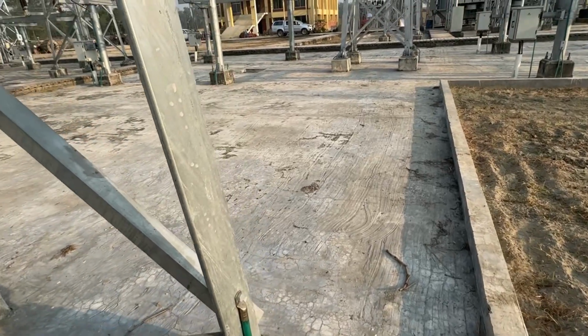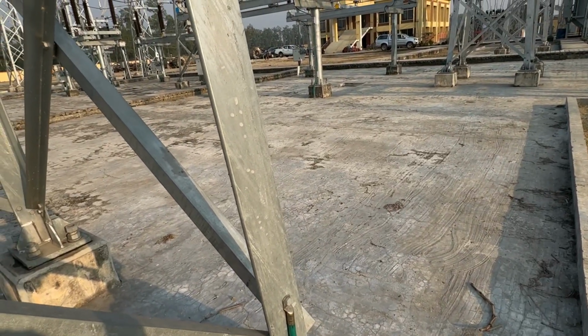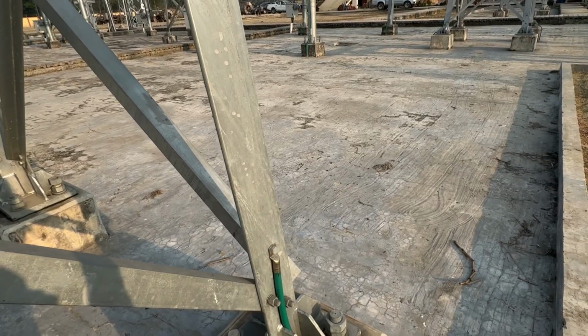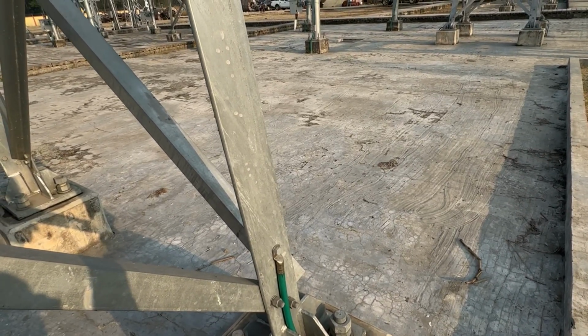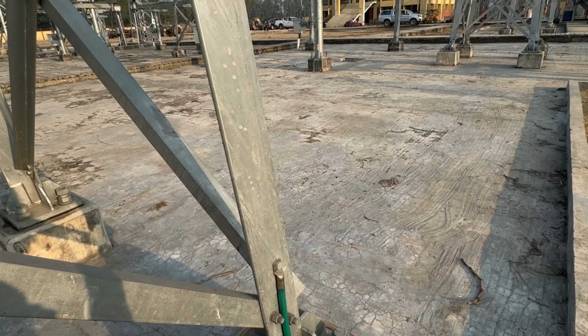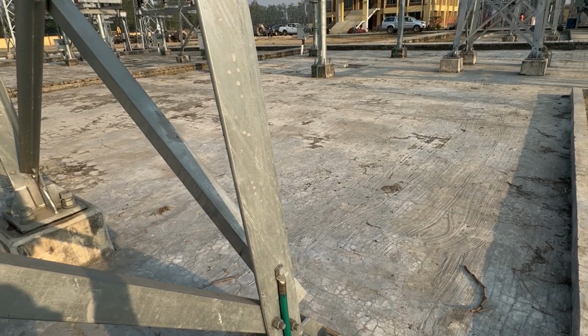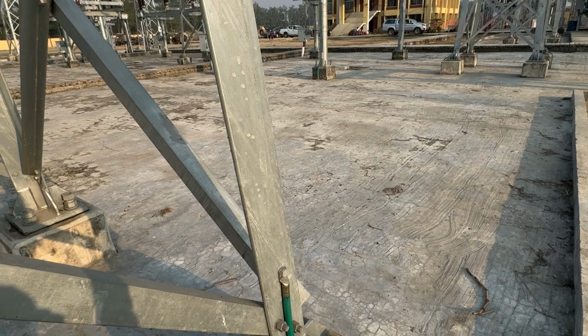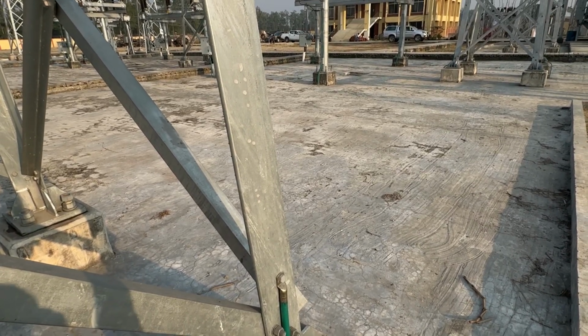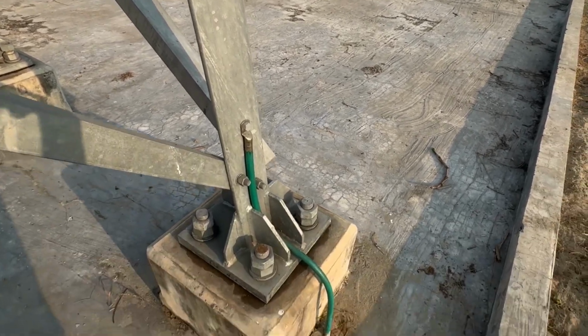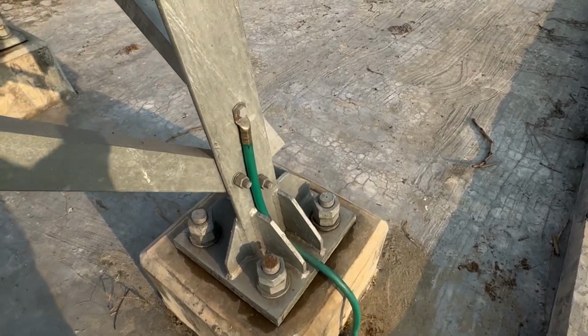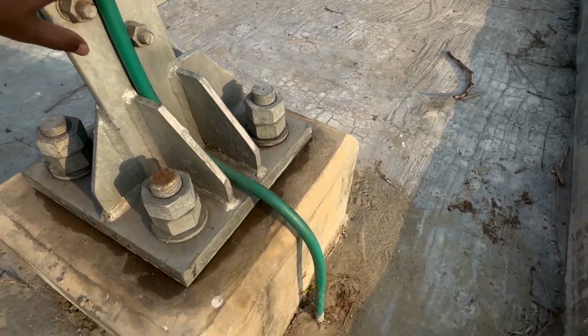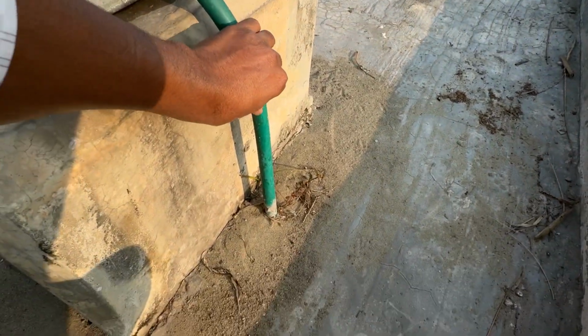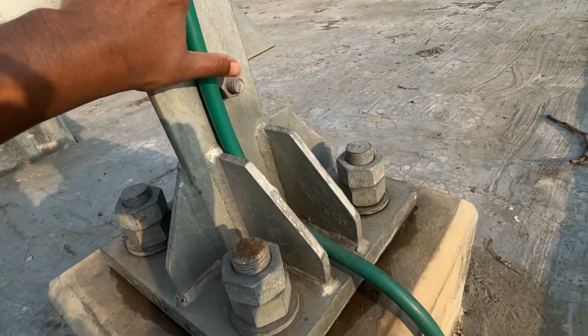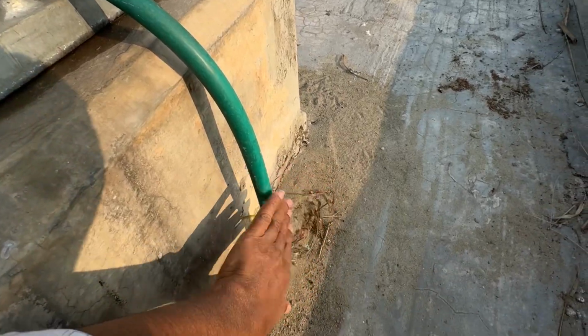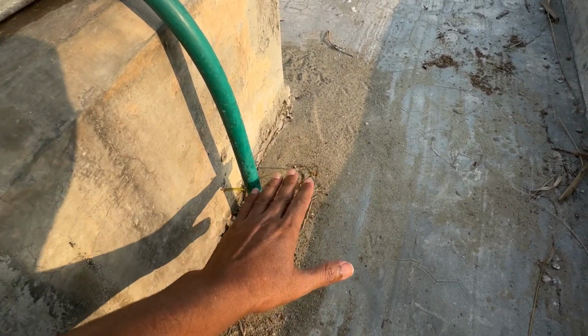It is mentioned that every equipment of a high voltage substation must be connected to ground to avoid any electric shock for maintenance purposes. Not only for maintenance, but also for safety of the equipment, ground is mandatory at the grounding point. These are grounding. It is connected through this gantry structure to the earthing mesh below this surface.